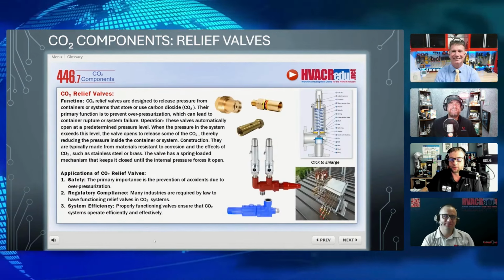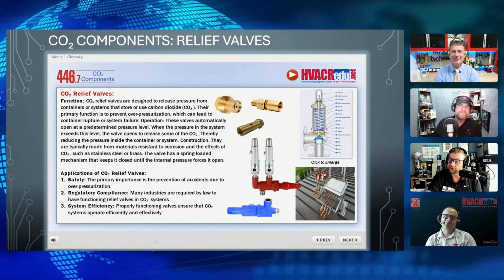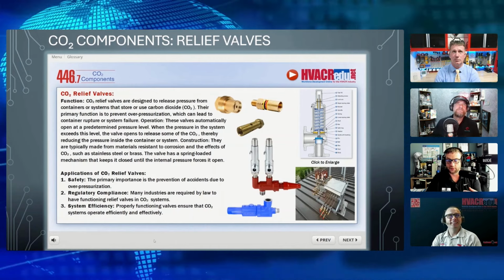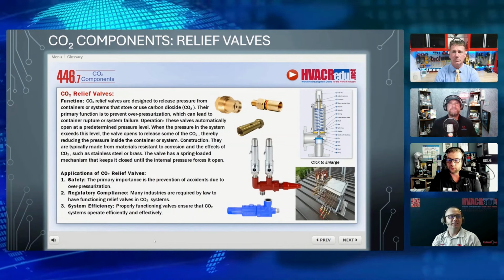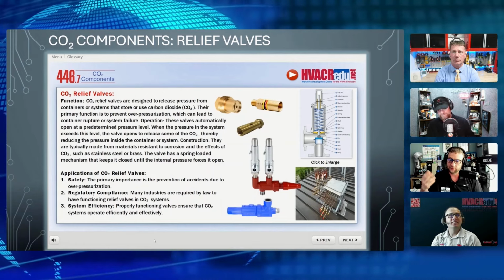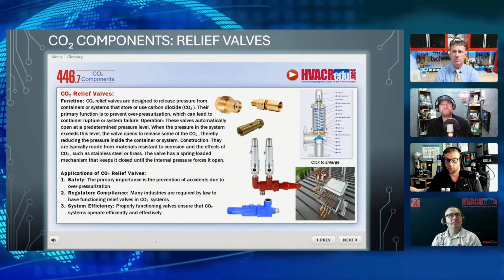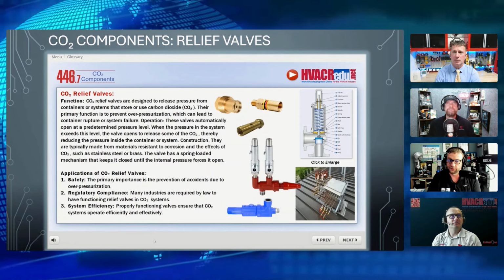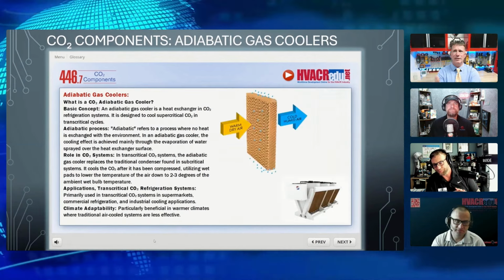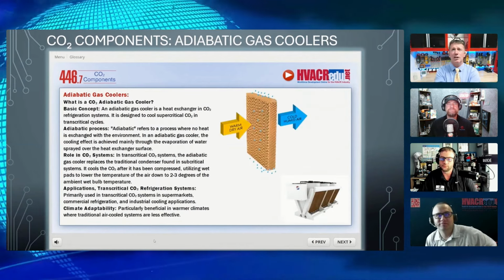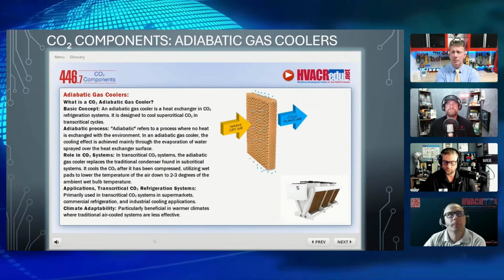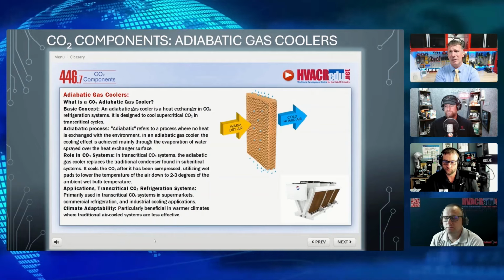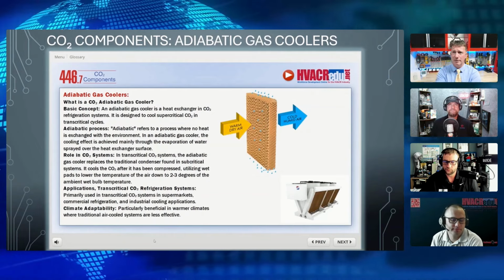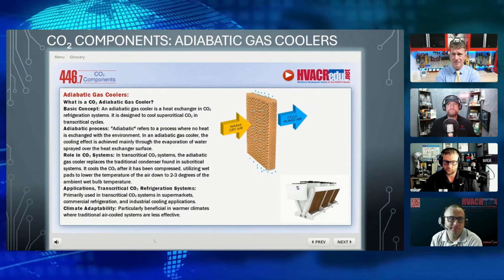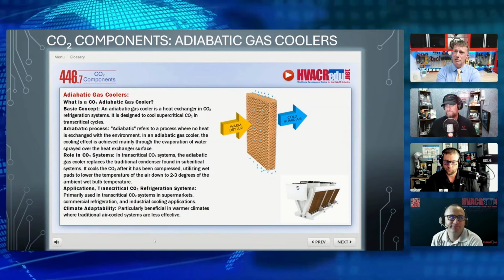All right. So the reason why we have a relief tree, once again, we talked about leak detection, right? And the safety concerns, right? So all the CO2, if we were to have a release, is going to vent and be outside because we don't want the relief venting within the facility. Go ahead. Absolutely. And relief valves are nothing new to refrigeration or air conditioning systems. A lot of people don't realize this. Even most of your residential systems will have some type of a relief device, which is just a safety pressure relief in case you get to an extremely high pressure.